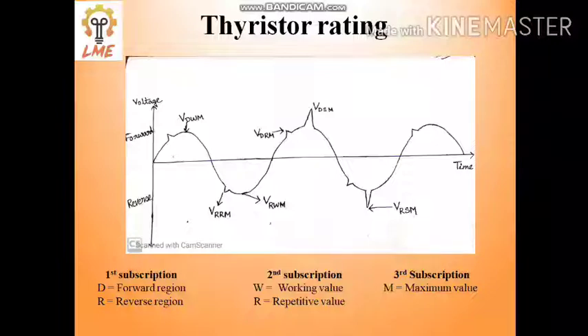Otherwise, if you use a Thyristor whose data sheet VDSM value is less than the practical value of circuit VDSM, then suppose one time the surge value will be more than the Thyristor's working surge value, and the Thyristor will be damaged. So we have to look at this particular point before using a Thyristor. Okay, so this is one part of the Thyristor rating. So let's go to the next slide.